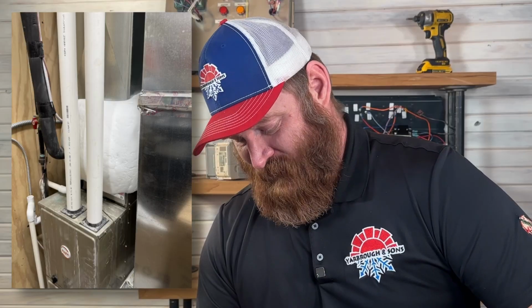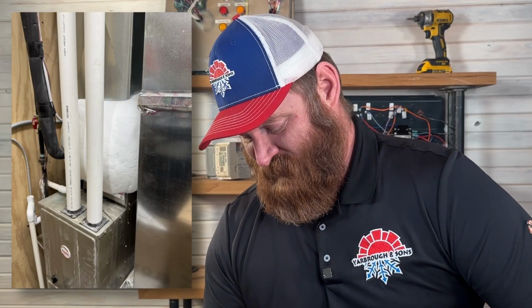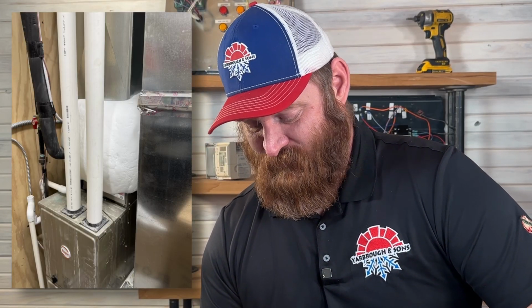It freezes that coil. The pressures are running too low because of the outdoor temperature. I don't know if I've seen one that bad though. I've seen about half an inch of ice around the outside, but that looks like it's about 3 inches, and judging by everything on that furnace underneath it, it doesn't look like this is the first time that's happened either.